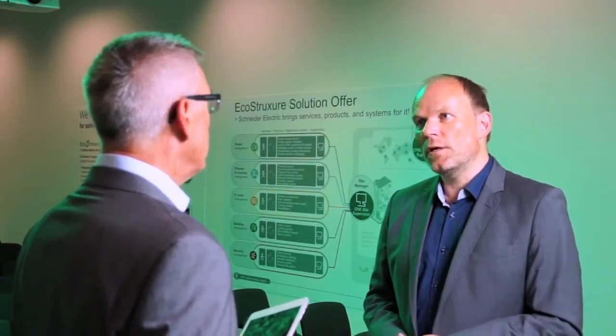Does this mean the customer needs to go and further instrument the data center? If the customer already has instrumentation in terms of temperature sensors at a decent density level, it's completely fine. He doesn't need to do more. But if not, he needs to install at least at every third rack a new temperature sensor or 2 new temperature sensors. And with that information, we analyze that temperature map, and based on that, we will actually adjust the CRAC units to fulfill the entire picture there.